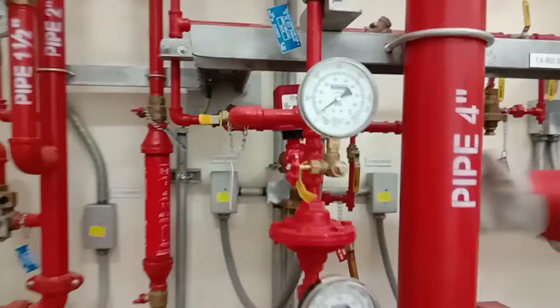Now how will this work, right? We explained a lot on the whiteboard, so I'll just go quickly through this one. Once we have water pressure from this side and air pressure from this side, the air from the top side is holding the water in the normal case. When there is a fire, the sprinkler system breaks, and the air will release from the top, causing the spring to go up and loosen, and this one will open. The moment it opens, the water will discharge from this line. This is the drain line.